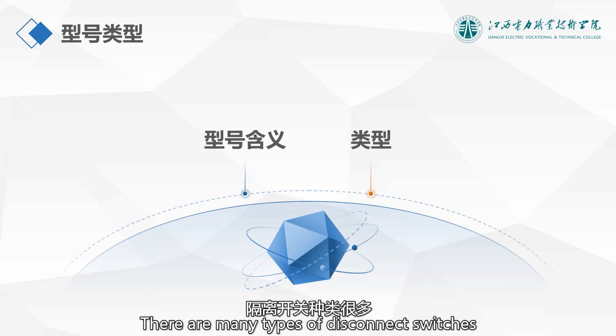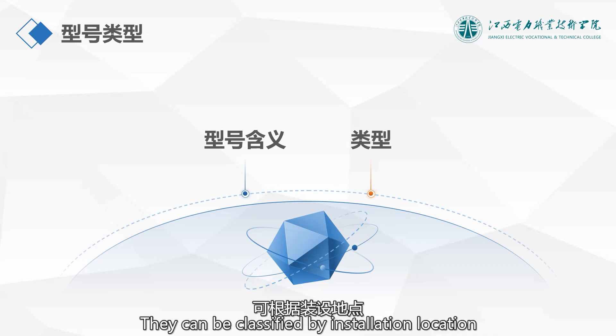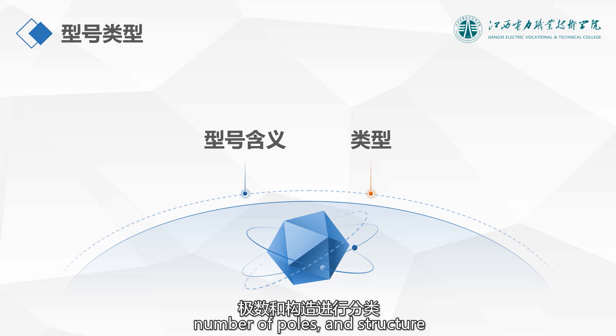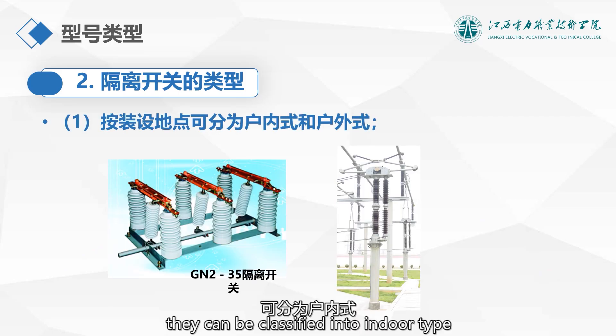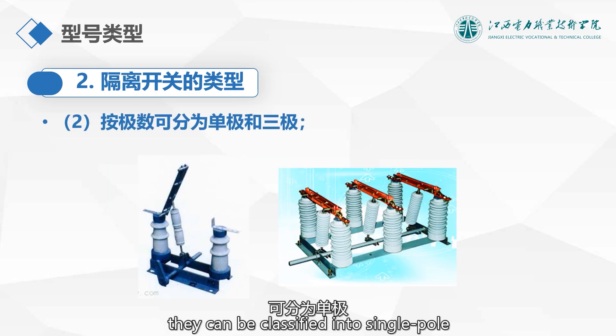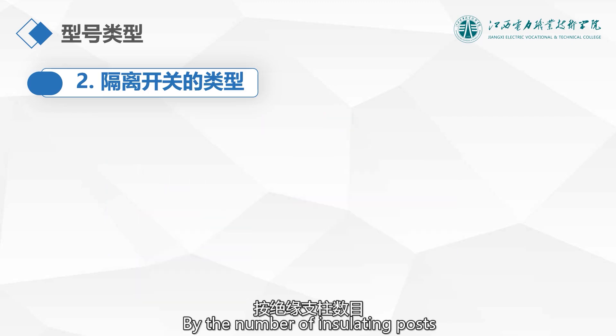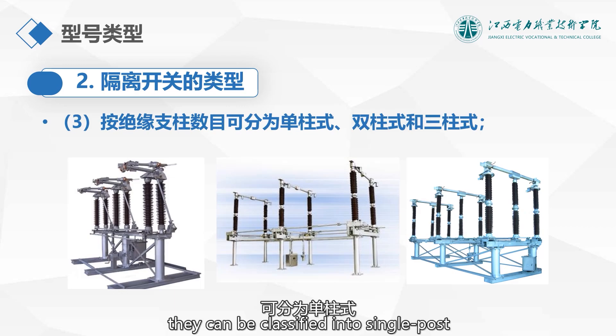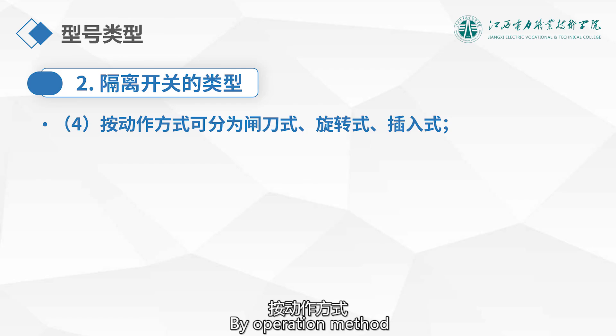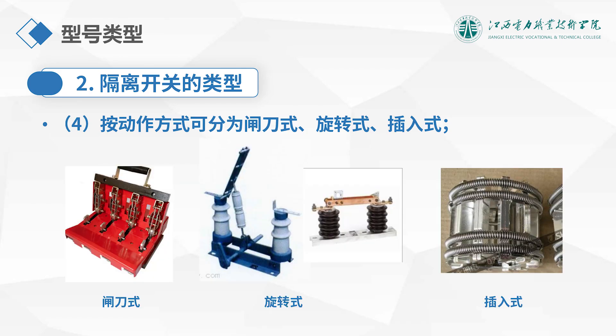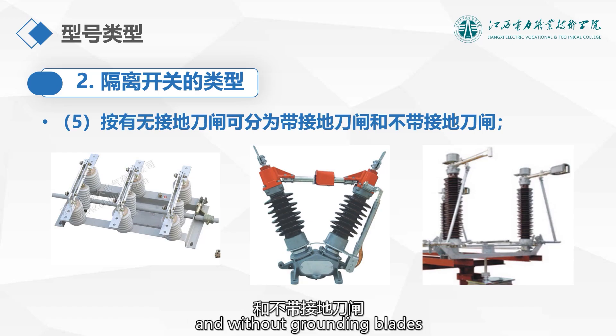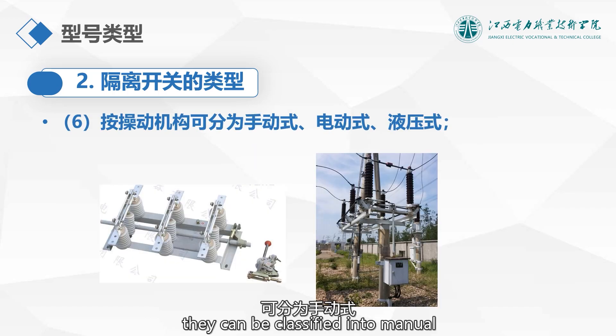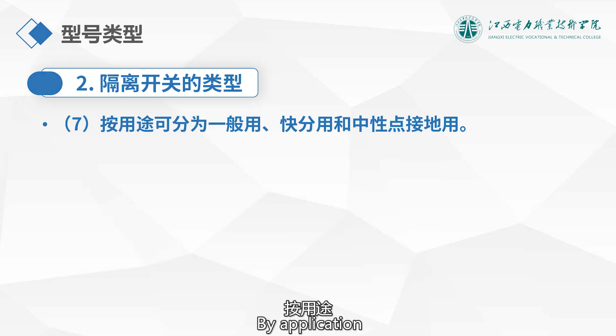The classification of disconnect switches: there are many types. They can be classified by installation location into indoor type and outdoor type; by number of poles into single pole and three-pole; by number of insulating posts into single post, double post, and triple post; by operation method into knife switch type, rotary type, and plug-in type; by presence of grounding blades into with or without grounding blades; by operating mechanism into manual, electric, and hydraulic; and by application into general purpose, quick break type, and neutral grounding type.